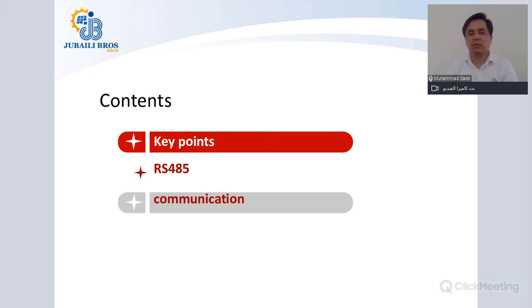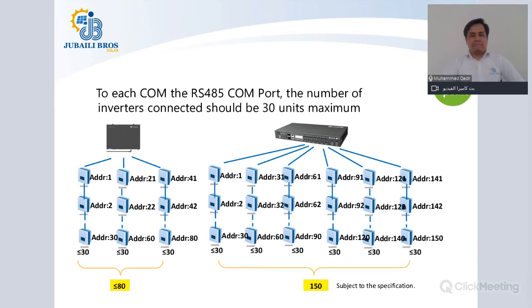RS485. So one way is the MBUS, which is normally used for bigger projects having termination on the MV side. But the RS485 is the most commonly used way of doing communication of solar inverters to the smart logger. We have two different types of smart logger: the smart logger 3000A, the smaller one, and the smart logger 3000B. Smart logger 3000B comes in two versions. The bigger version has 6 COM ports, and the smart logger 3000A has 3 COM ports. Now, to each COM port, HUAWEI recommends to connect up to a maximum of 30 solar inverters in a daisy chain, not more than that. So it could be from 1 to 30 solar inverters going to one COM port of your smart logger.